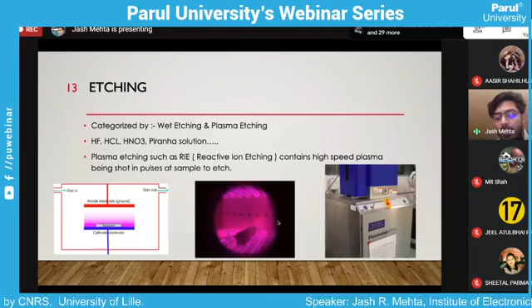So after etching, we need to check our sample. So here it is. We can see it is a scanning electron microscope. So here, basically this microscope works with a high voltage electron beam gun. So the beam is up to 10 kilovolts of electron beam. It will throw the electrons on the surface of your sample, and this will generate the image in return. So let's see in the picture how the SEM looks like.